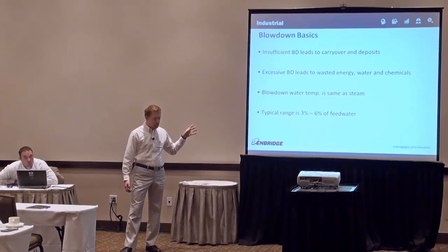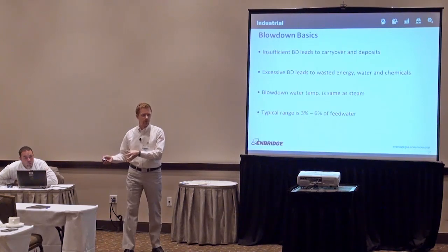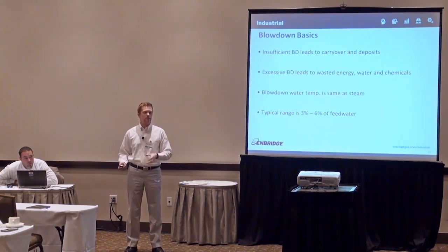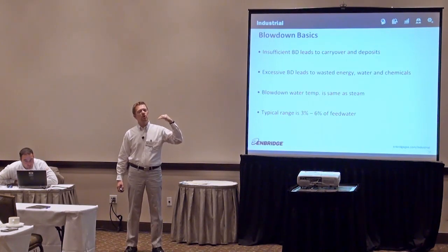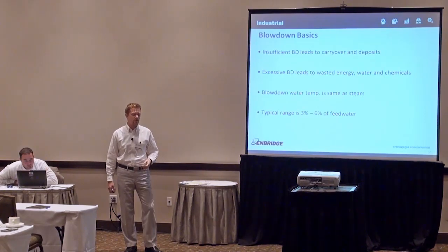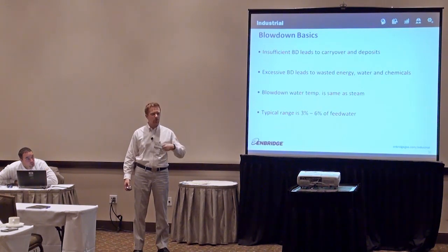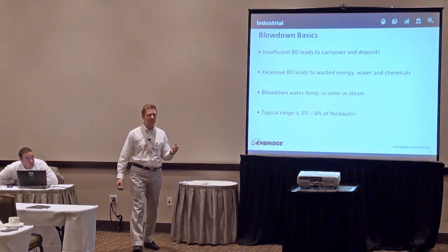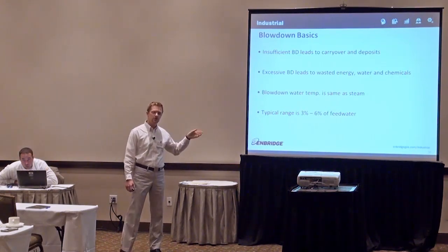The percentage of blowdown varies dependent on a number of factors, predominantly the water quality that you're bringing into the system. Like I said, you've got a lot more minerals in groundwater, which means you can concentrate that boiler up fewer times than you could if you had nice pure water coming into the system. So in Southern Ontario, I'd say typically, in the GTA, we're probably concentrating that water about 10 times before we have to drain some out of the boiler. I know if you were up in Guelph, it's probably no more than 4 times. So you're putting a lot more water down the drain, and chemicals and fuel associated with blowdown.